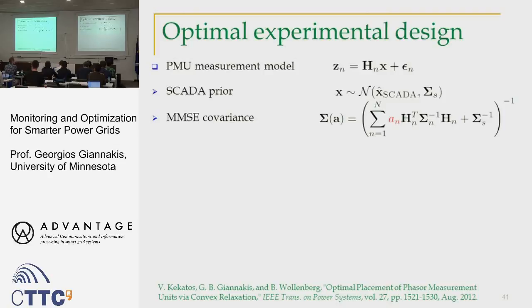What we came up with is an approach known in statistics as the optimal experimental design approach. Per node, we have a measurement model that is linear, and we utilize the conventional SCADA measurements as a prior. Using Bayesian statistics — or you can consider it as a regularizer — our argument is that the true state vector is random, distributed with a mean equal to what we have found from SCADA. The mean of the Gaussian is taken to be the conventional SCADA estimates, and the covariance is their confidence interval of uncertainty.